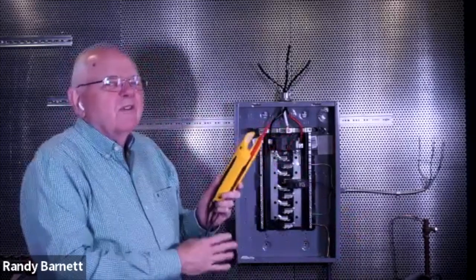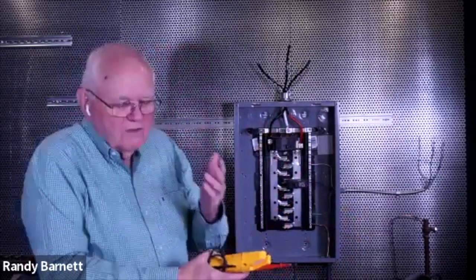So you've got to read that one, right? You're going to have to study that one and do a little calculation there if you get involved in that. Chapter 9, Table 8, right? It has all of your areas for your different conductors and your circular mil areas and all of that.